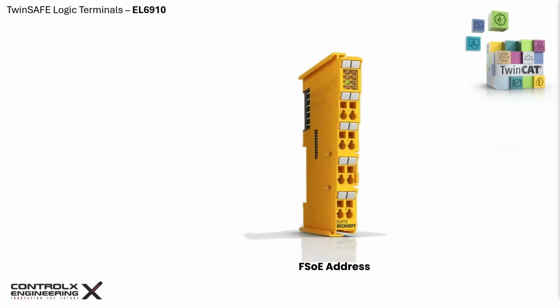Before you snap the yellow terminal onto a DIN rail, stop and look at the side. You will see a small block of dip switches. This isn't for decoration. It is the hardware key to your safety system. Standard EtherCAT terminals are identified by their position in the lineup. If you swap two identical EL1008 input cards, for example, the PLC doesn't care. But in functional safety, position isn't enough.